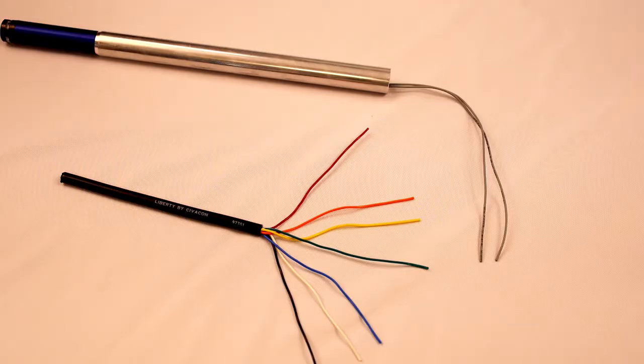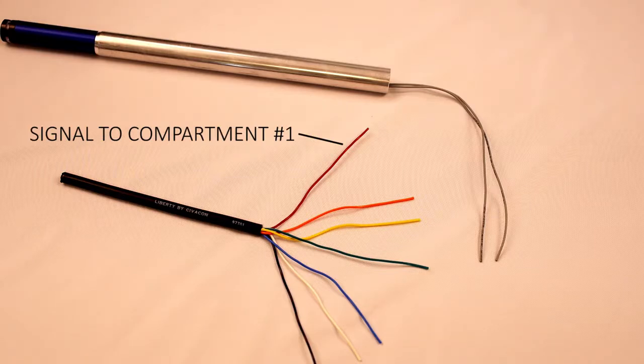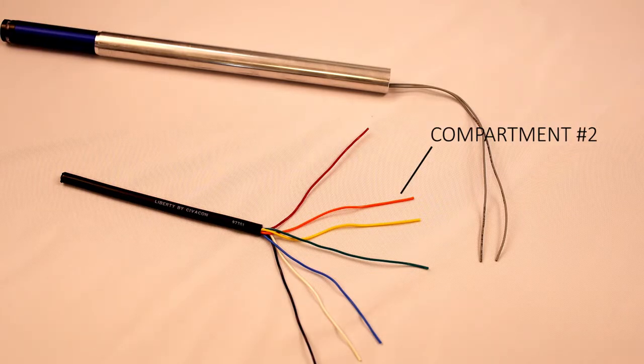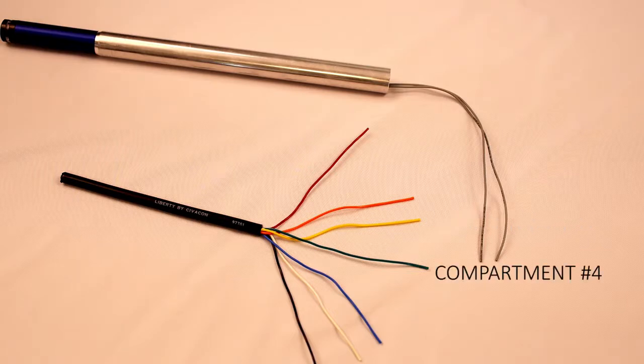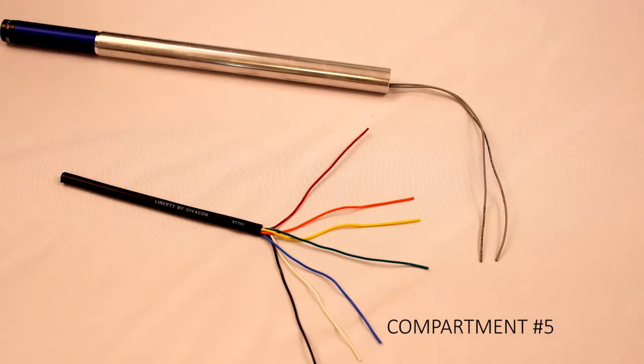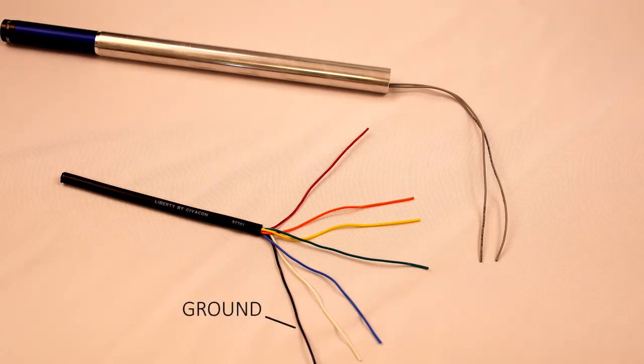Here we have an example of a 2-wire overfill probe and the main cable running from your onboard monitor up to your probes. We're just going to take a brief second to talk about what the different wires do coming from that main cable. The first wire, the red wire, is what's sending the signal or pulse to compartment number 1. So red is your compartment number 1, orange is number 2, yellow is number 3, green is number 4, blue is number 5, white is number 6, and black is your ground.